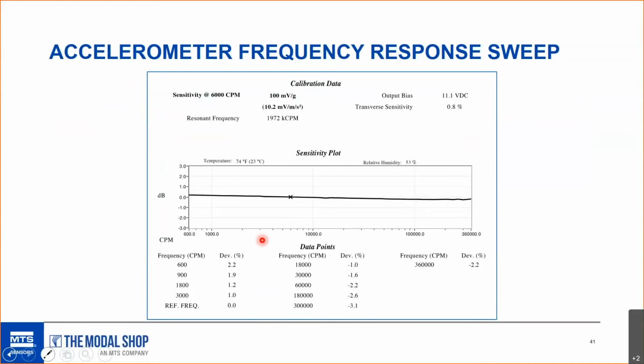So this is an accelerometer frequency response sweep, and you can see the sensitivity of this transducer at the top of the screen. It was 100 millivolts per G. This sweep is done in cycles per minute, so 1 hertz is 1 cycle per second. So 1 hertz is equivalent to 60 CPM, and 100 hertz is 6,000 CPM. So that's why the sensitivity is written there at 6,000 CPM.